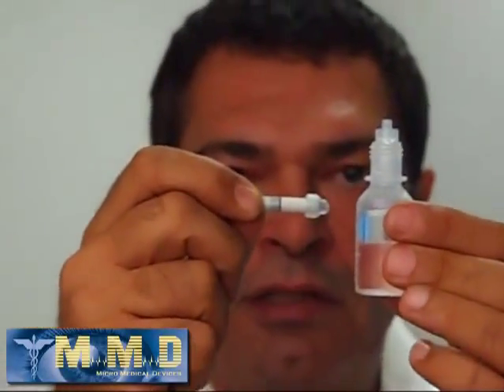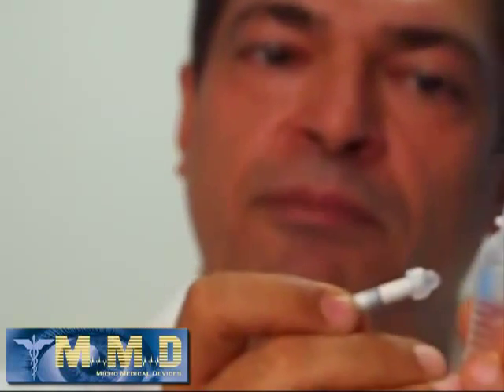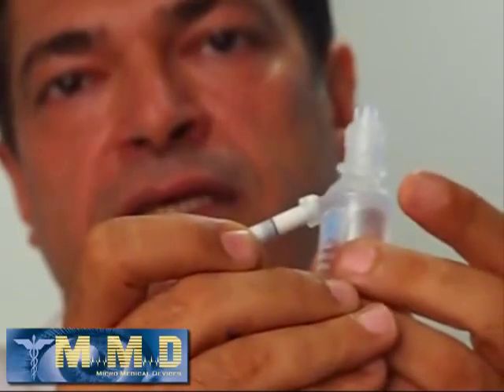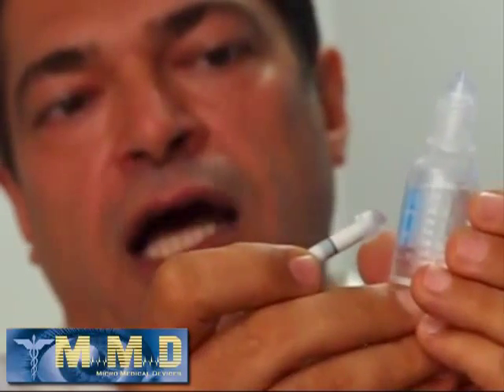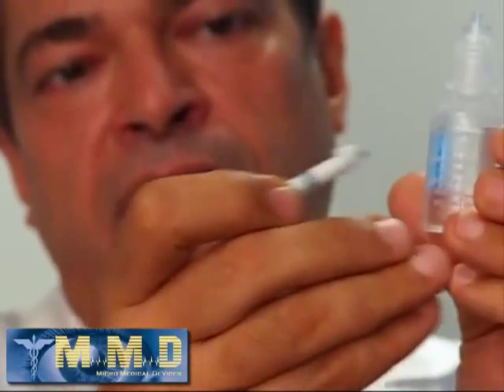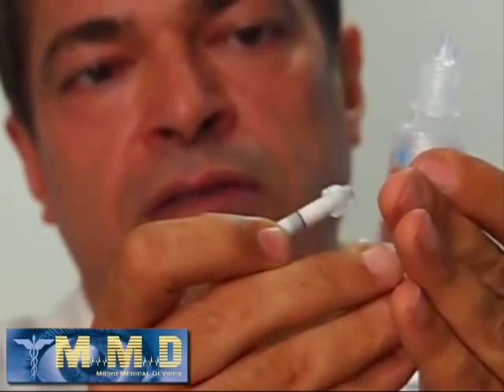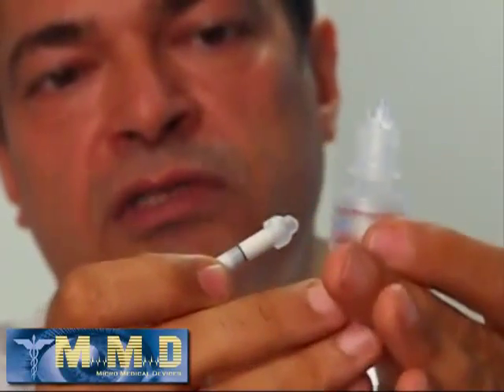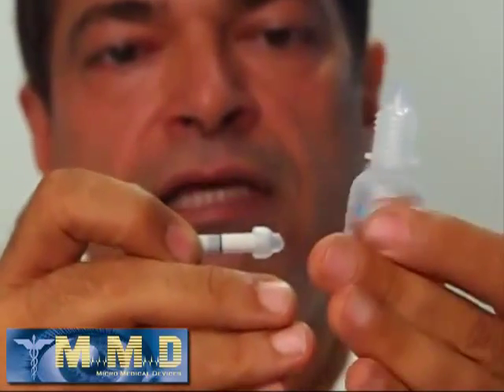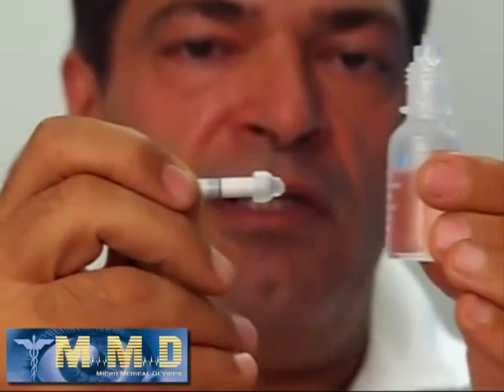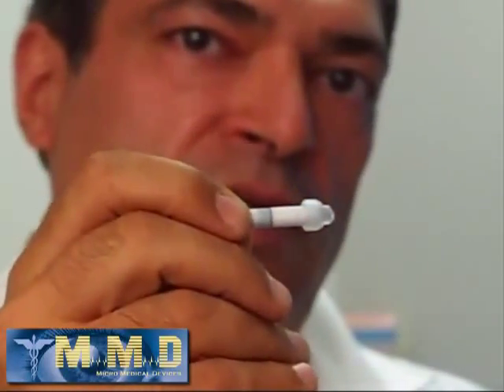Next, you want to make sure that when you approach the cornea, you approach it straight on. The patient does not have to be tilted back in this particular scanning apparatus, but what you don't want to do is press too hard on the eye, or approach at an angle that causes the meniscus to be drained completely. So if you touch the eye like so, at an oblique angle instead of a perpendicular angle, you make an avenue for the water to seep out instead of staying inside the container. So just approach the eye straight, and once the tip touches the eye, do not force it into the eye, just hold it on the eye and instruct the patient to look at the blinking light.